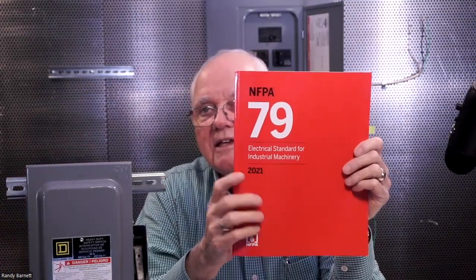Also, that brings up something else. We also have the NFPA 79 standard, the electrical standard for industrial machinery. All of Chapter 5 in this book is dedicated to disconnecting means for industrial equipment. Without going through all of that chapter, the bottom line is that when we throw that one disconnect handle, we want to de-energize not just the motors themselves, but also the control circuits, anything that is powered inside that control cabinet. That's the general rule, but there are a lot of other requirements for disconnecting means on industrial machinery.